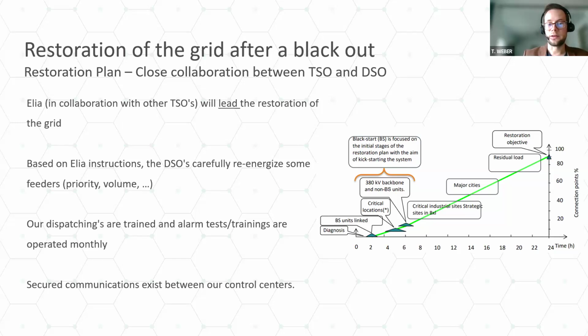And our control centers are trained, and every month we make some tests between ELIA and the DSO, with alarm signals between our SCADA and ADMS. So some alarm signals are sent back for acknowledgement. So there are some tests and trainings that are very important to be ready in case of, even if we all hope it will never happen. And we have secure communication, of course, between our dispatchings, DSO and TSO, to make it blackout proof.